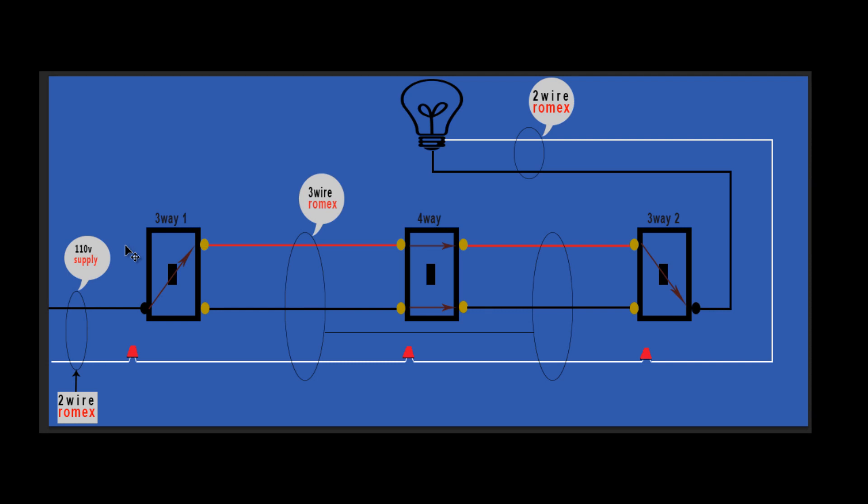But that's actually a topic for a whole other discussion there, and I'm going to try my best to stay on point here because that's not what this tutorial is about. It's about four-way switches, but I just want to make it really clear that you should never have a situation where you have your neutral conductor or your grounded conductor connected to the actual switch. Not in a residential situation anyway. I mean, there are cases in some control circuits and control systems where you might have a neutral conductor that goes across contacts for overloads and things like that. But that's, again, that's a whole other subject.